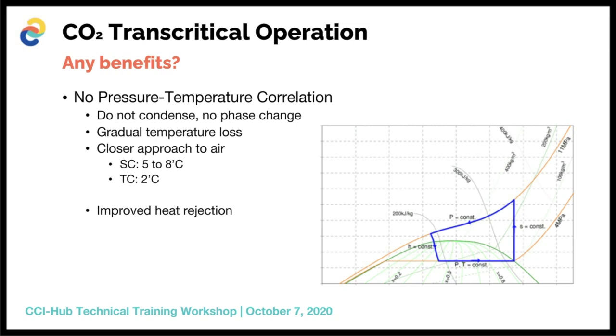In subcritical mode, when condensing a refrigerant, you allow for a temperature difference of about five to eight degrees Celsius between the refrigerant and ambient air. With CO2 in transcritical mode, this is only about two degrees Celsius because of the closer approach. This means you can still have a lower gas cooler outlet temperature even at higher ambient conditions. Additional benefits come when utilizing this for heating purposes, where CO2 in its transcritical state provides very good heat rejection.